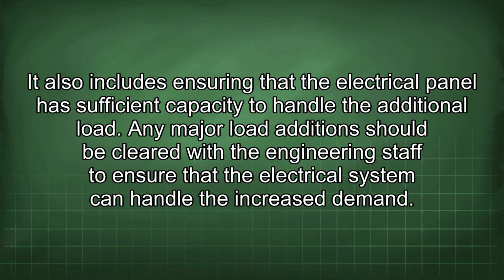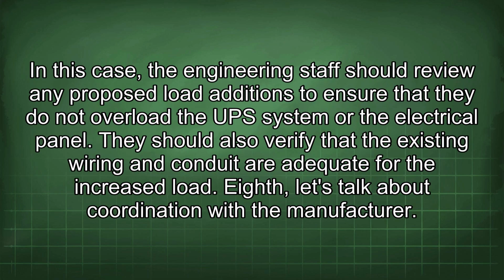Any major load additions should be cleared with the engineering staff to ensure that the electrical system can handle the increased demand. In this case, the engineering staff should review any proposed load additions to ensure that they do not overload the UPS system or the electrical panel. They should also verify that the existing wiring and conduits are adequate for the increased load.